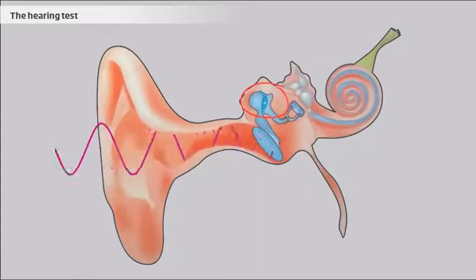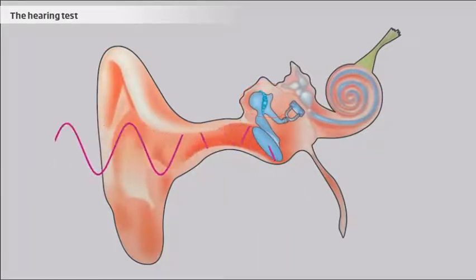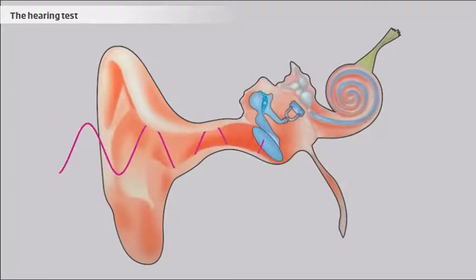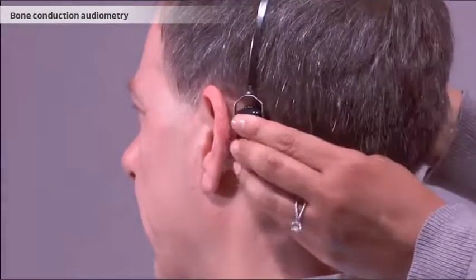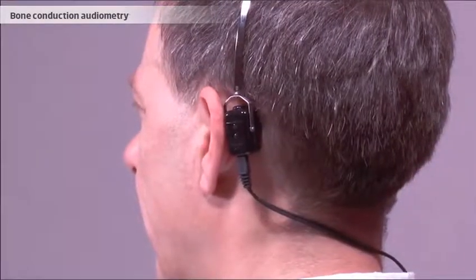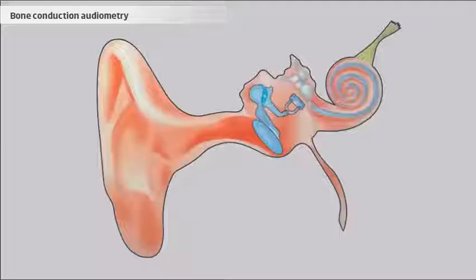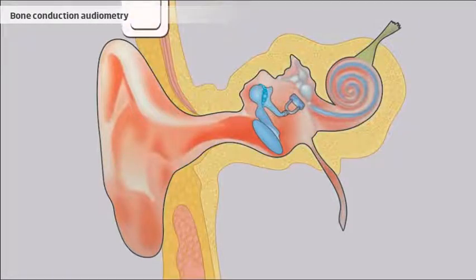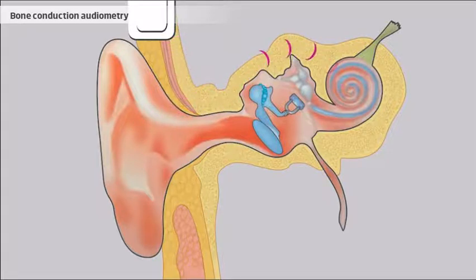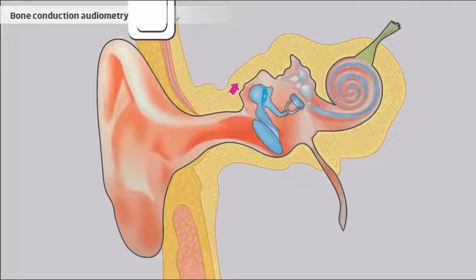However, there may be an obstruction in the middle ear which prevents sound waves from reaching the inner ear. To make sure there is no such obstruction, it is a good idea to perform bone conduction audiometry. This allows the hearing threshold to be determined independently of how the middle ear functions. A bone conductor is a vibrator that is placed behind the ear. The sounds from the bone conductor are transmitted through the cranium and activate the inner ear directly, bypassing the middle ear.